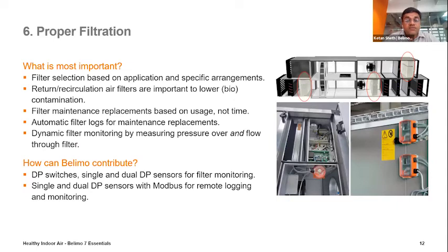Now we come to the topic of filters. The filter plays a very important role, and MERV 13, MERV 8 and other ratings have become very, very important after COVID came into the picture. I have also seen some UV systems come up, installed in the ducts and the AHUs, so that wherever return air is coming, the UV also obstructs the spread of virus. So filter selection is very important based on the application and specific arrangement. The return air filters are also important for absorption of the contamination.